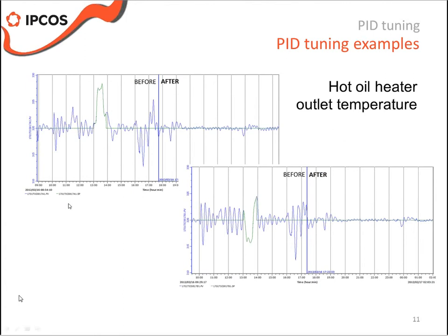And then after that, what we did was collected the data and entered it into our software and did the tuning. And you can see the before and after scenario here. A significant improvement in the exit temperature of the hot oil heater.